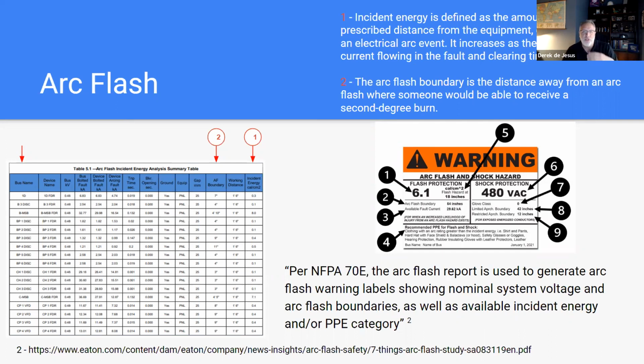Your SCCAF report should start with, hopefully, the same model—the same SKM model or Power Tools model that developed that report. Otherwise, the person developing the report will have to build the model further upstream to make sure their breakers are properly coordinated for the short circuit available fault current at that breaker.